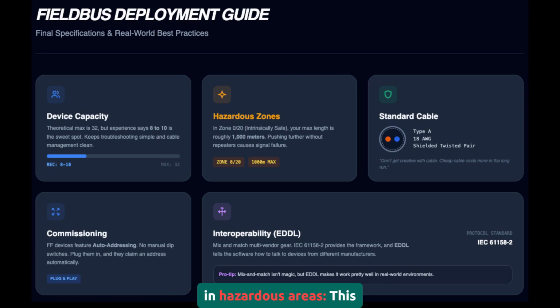Segment lengths in hazardous areas. This one bites people. You're in zone 0 or 20. Intrinsically safe. Your max is roughly 1,000 meters. If you try to push it further without a repeater, you're asking for problems. Plan accordingly. Cable. Type A, 18 AWG, shielded twisted pair. That's the standard. Don't get creative. I've seen people try to use some other cable because it was cheaper. It wasn't cheaper after 3 weeks of false alarms and re-terminating.